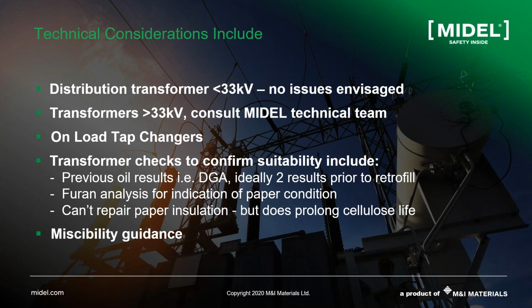And finally, for retrofilling, we need to consider what the original liquid is. This is the miscibility guidelines. Usually, if you have mineral oil or any other ester, natural ester or synthetic ester, in that transformer, you can retrofill with an ester. But if that transformer has silicone liquid, we cannot retrofill it, because silicone liquid and esters are not miscible, and they will not mix homogeneously.